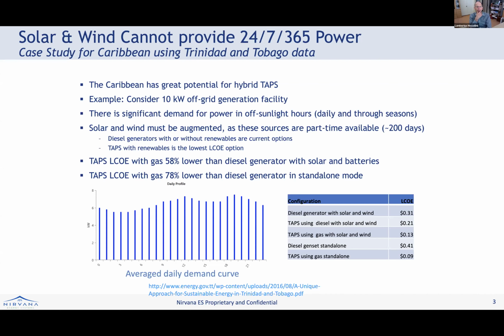As an example, if you took a 10 kilowatt off-grid generating facility, you still need to provide significant amounts of power outside the solar installation time periods, and demand curves vary over time. So to do a careful analysis, it's important to note that saying you have 3 kilowatts of power is misleading, because as typically specified, that's only at noontime.